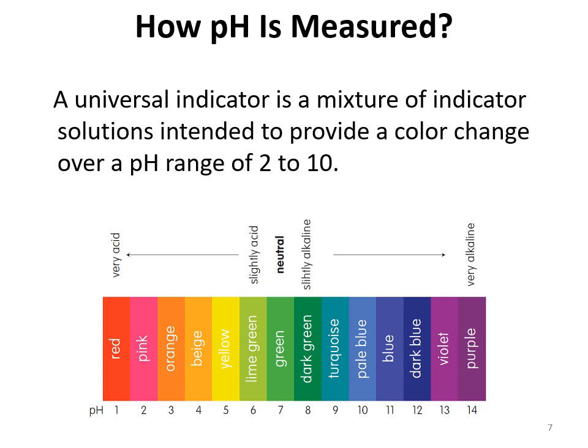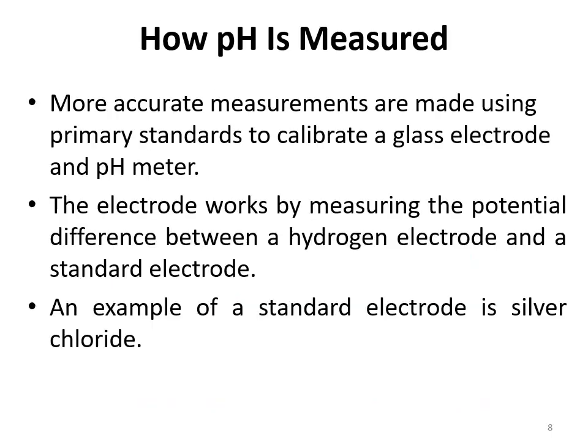Next we will discuss how a pH meter, or potentiometer, works for pH measurement. The most common approach is the use of a specially prepared electrode designed to allow hydrogen ions in the solution to migrate through a selective barrier, producing a measurable potential or voltage.